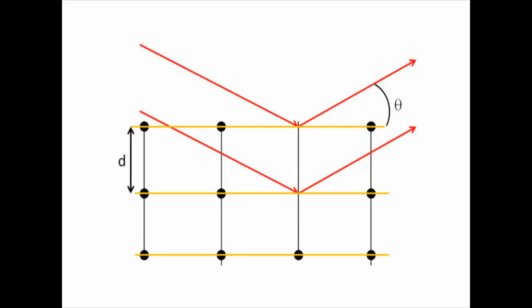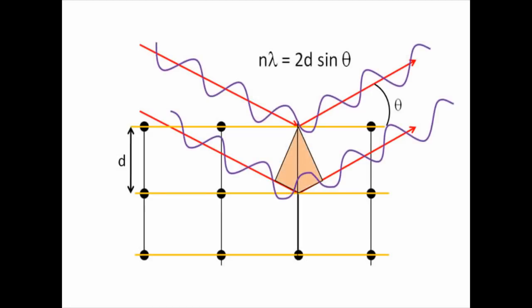Wider slits give more energy but have wider peaks. Smaller slits give less energy but better resolution. The beam also passes through a nickel filter which removes the k-beta energy before the diffracted beam enters the detector. X-rays at angle theta are reflected from internal crystal planes separated by distance d. The Bragg diffraction results from constructive wave interference when the quantity 2d sin theta is an integral number of wavelengths.